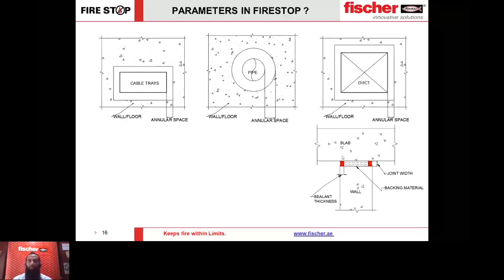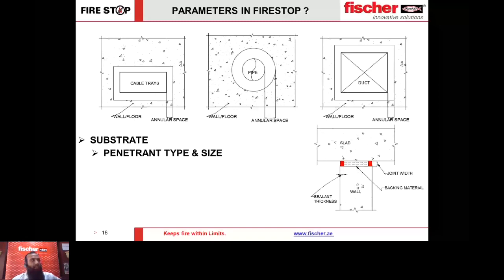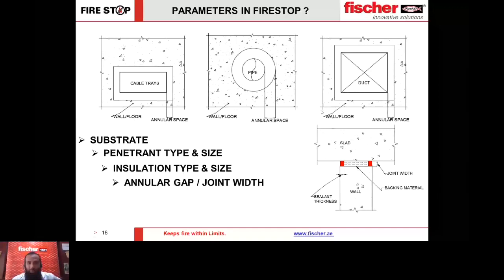Some important points to remember: fire stopping always depends on the substrate — what is the floor or wall made of, is it gypsum drywall, concrete, or block wall, and what is its rating? Then: what is the penetrant type, what is the penetrant size? What is the insulation on top of the service — its type and size? And very importantly, the annular gap — the gap between the service and the opening. Then there is joint width and the backing material used.